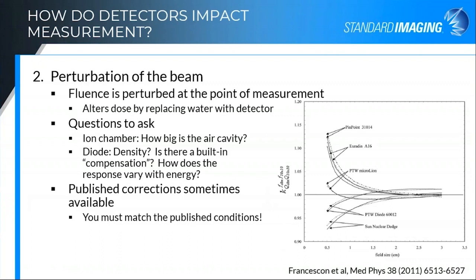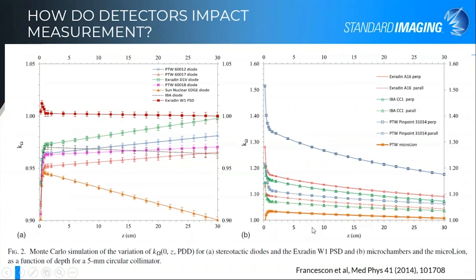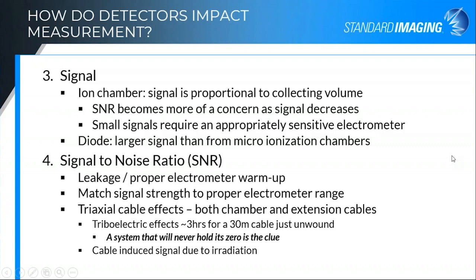Published corrections are sometimes available for detectors. It's good to look for those, but remember that if you're going to apply published corrections, you need to match the published conditions, because if the conditions are different the corrections may be different as well. One of the plots from Paolo Francescon's paper shows our scintillation detector compared to some of the other diodes. Ionization chamber comparisons with the PTW microLion are shown as well.